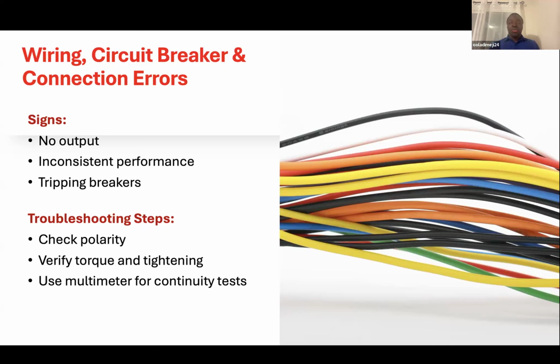Perhaps you can also have another issue where you put in 20 amps from one end of the cable, from the output of the inverter, and on the other end maybe you're getting like 12 amps or 9 amps. Then you have a voltage and current drop along the line, and you want to know what the problem is. In this instance, you want to look at why you are not getting what you should get. Although there is some acceptable range of current and voltage drop along the cable, it is not at the tune of having more than 8 amps drop within a cable. So those are ways to troubleshoot. But with that, maybe you now start looking at what your cable sizing is, because for every cable you have the cable gauge and the amperage that is set for each cable gauge size.